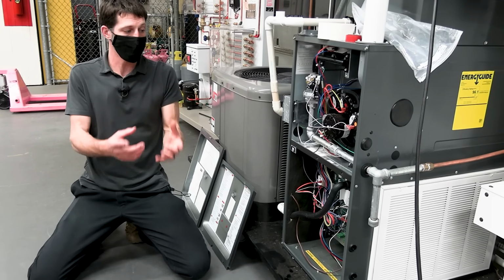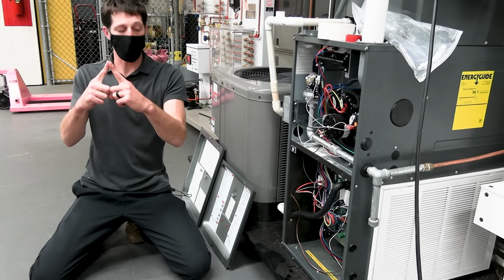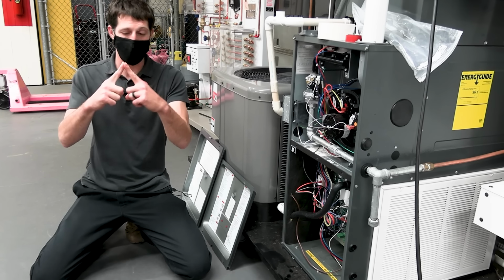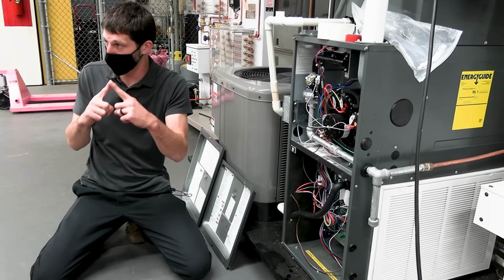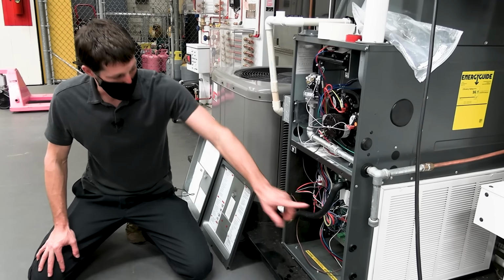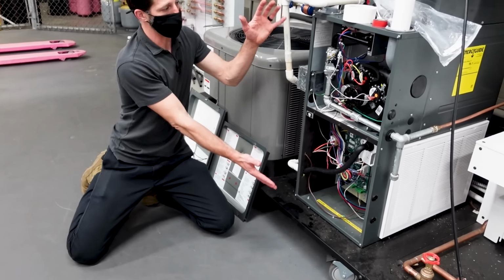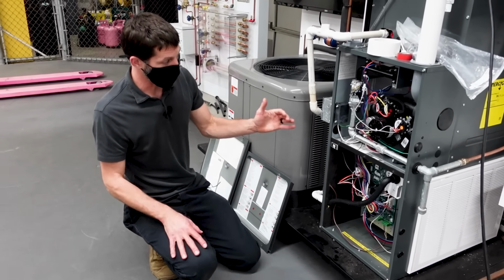So when you turn heat on, what's going to happen is R and W touch. The thermostat does not touch R and G. It does not turn the fan on. The control board tells when the fan is going to turn on based on the sequence of operation for heat, which I can just run you through quickly.